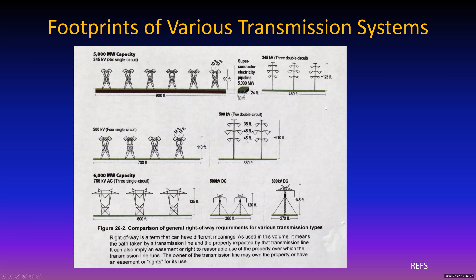Now let's take a look at that 800 kilovolt DC down there in the lower right-hand corner. 270 foot right of way, smallest of all, 145 feet tall. It's pretty high, but the big 765 kilovolt AC lines are 135 feet high, and 6,000 megawatts capacity takes 600 foot right of way. We're talking 6,000, or sorry, 5,000 megawatt capacity here with this big 800 kV DC. I don't expect too many people going to climb those poles, but we're probably going to see some of them.